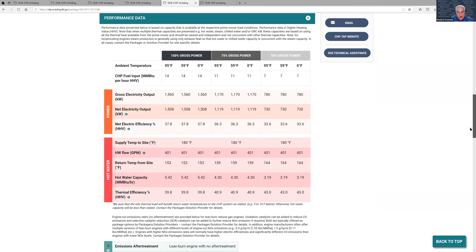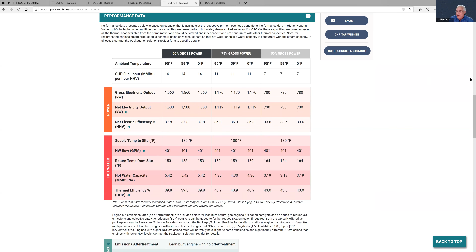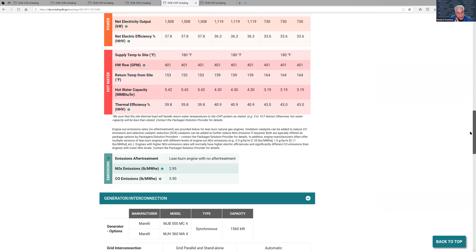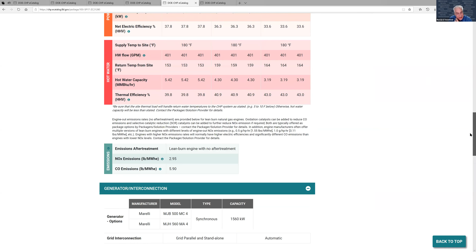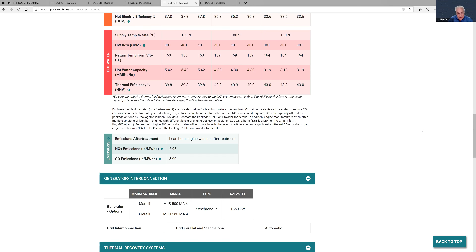You get the full output of the system at 100% gross power, 75% gross power, 50% gross power, and at 3 ambient temperatures. So you can get really good information here on the performance against the standardized hot water of 180 degree supply. But not only that, on lean burn engines you will get emissions for NOx and CO, which are required, and this is with no after treatment. Obviously, if you put after treatment on this, you can get it down to meet any standard. You can meet South Coast Air Quality Management District standard if you put oxidation catalysts and SCRs on it. So that is also available.